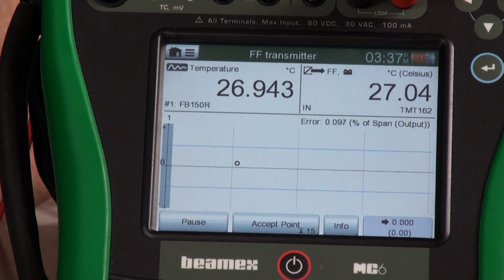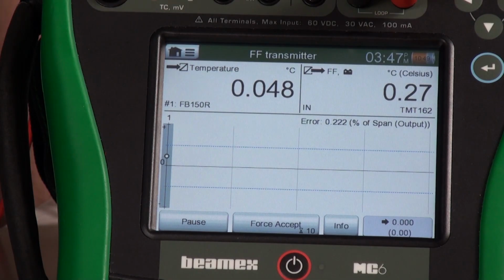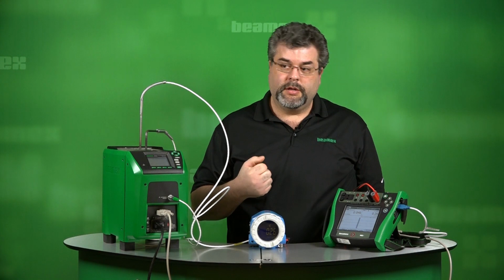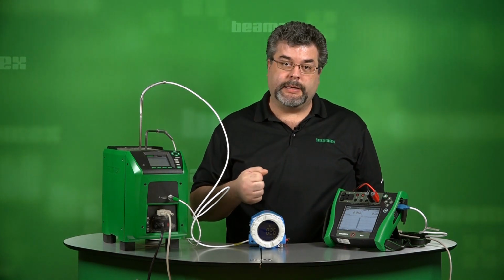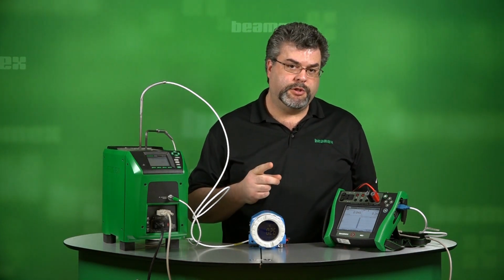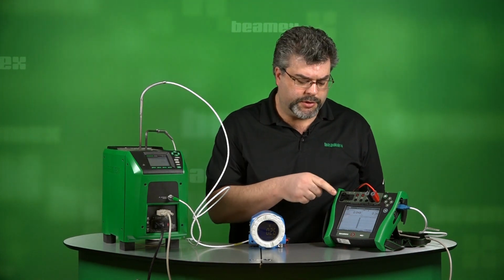The temperature block is driving to our first test point, which happens to be 0 degrees C. We've reached our first set point, and we have a predefined set point delay of 15 seconds, which is counting down at the bottom. As soon as it reaches 0, it will grab that test point and move on to the next. Right now, the temperature block is heating up for our second test point. While it's doing that, let me explain what's going on with the screen.